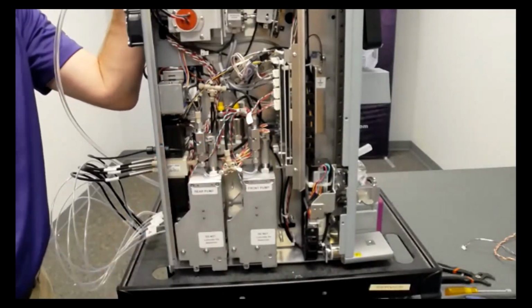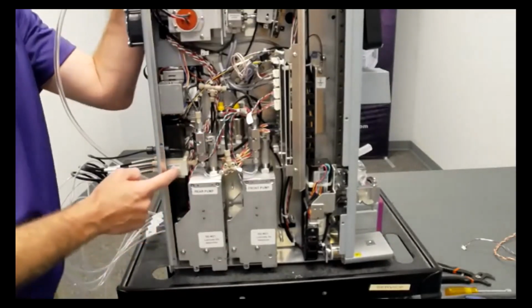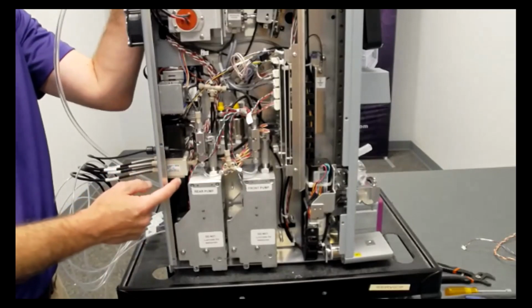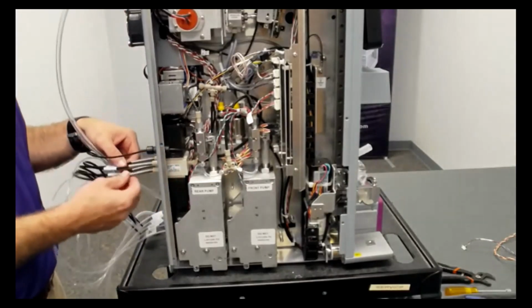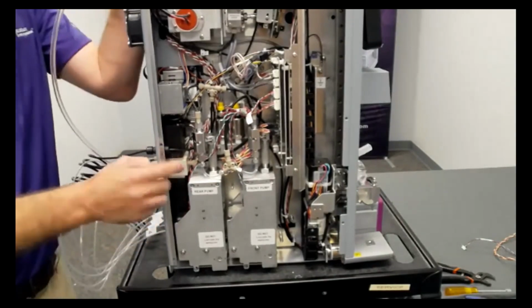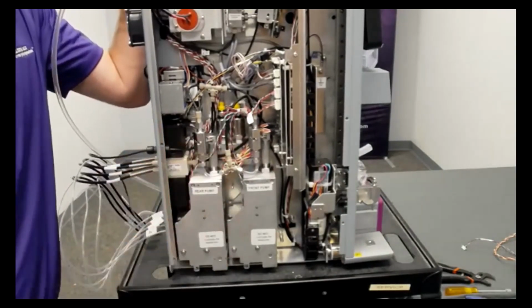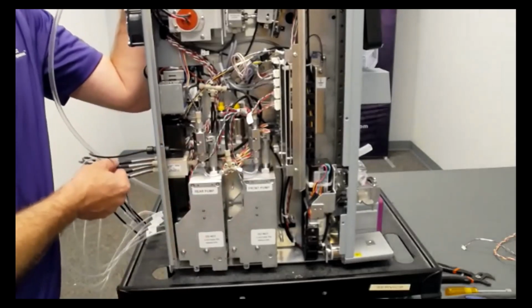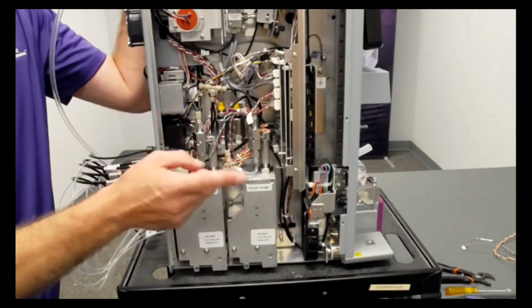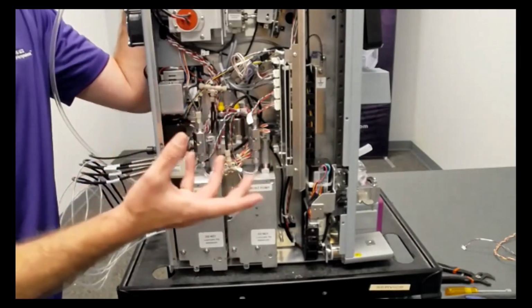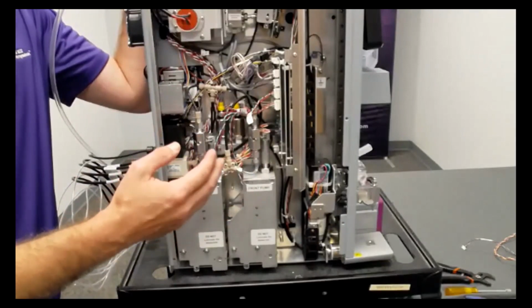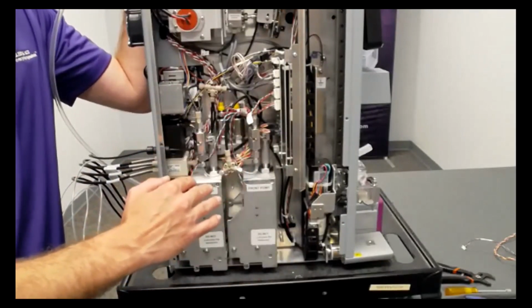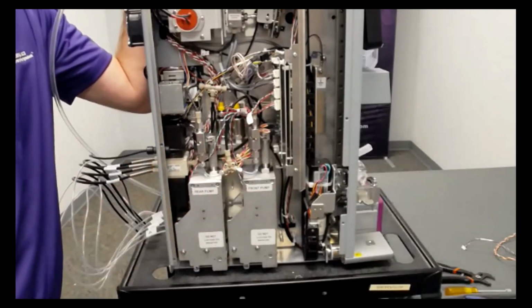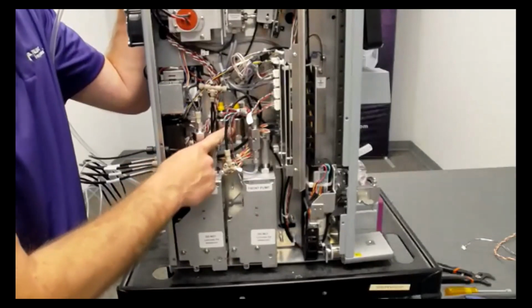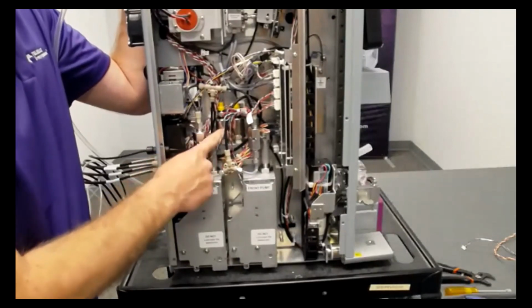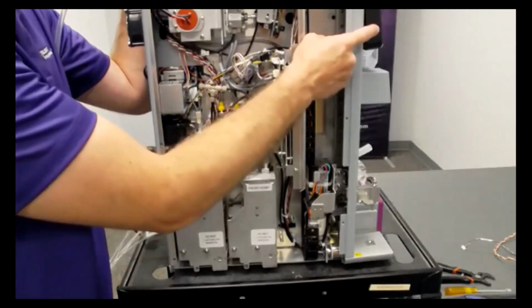Okay. Now over here, you're going to notice the solvent select valve or the solvent manifold. So you've got 4 inlet lines that can go into the NextGen. And this is what is toggling what's active to go into the pumps. All right. So if you're using 1 and 2 and you're setting up a gradient, this is toggling between 1 and 2, depending on what your percentage of B is on your gradient. So, you know, it's going to allow 70% of A in and then 30% of B in. This guy right here. Back behind here are the pressure transducers. This is what measures your overall system pressure. And that's what displays on your screen.